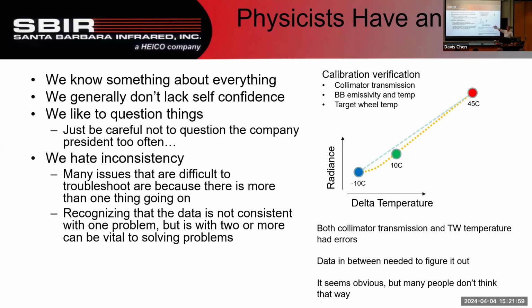You got to calculate it in between. So what was wrong with the collimator transmission? We were using the manufacturer's transmission taken from a test coupon, not the actual transmission measured through the collimator. So it should have been okay, and when they did their quick test, it looked okay. So they believed it, but it wasn't right.